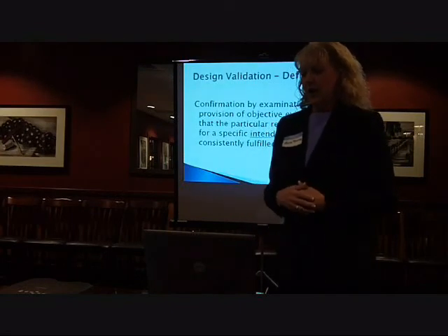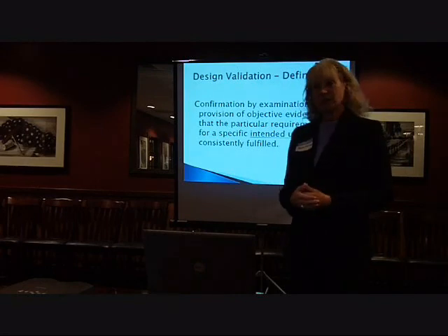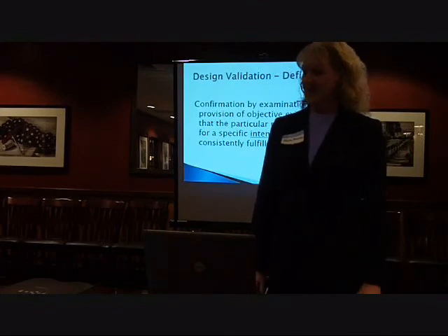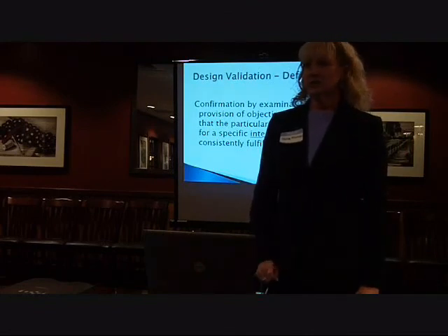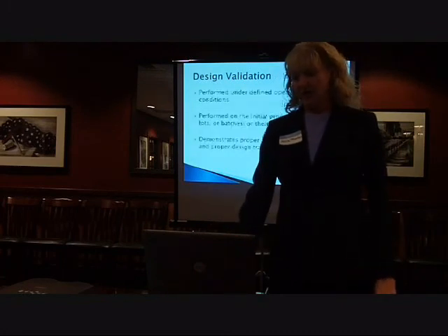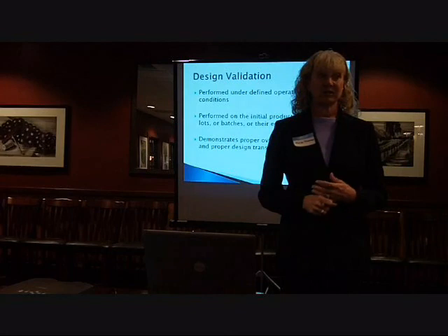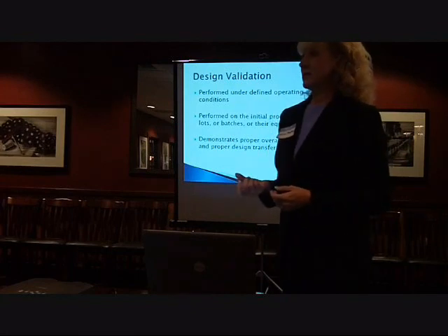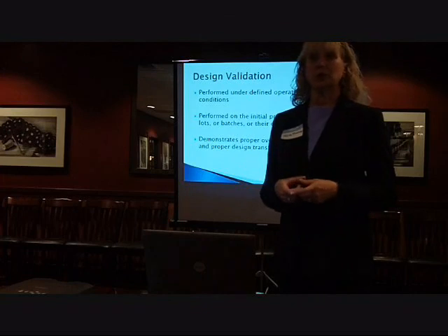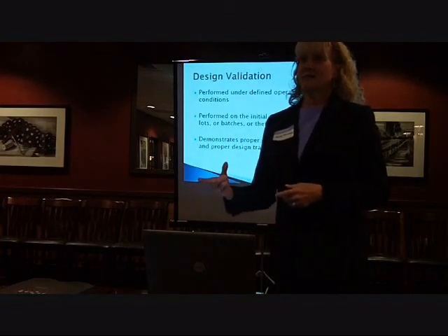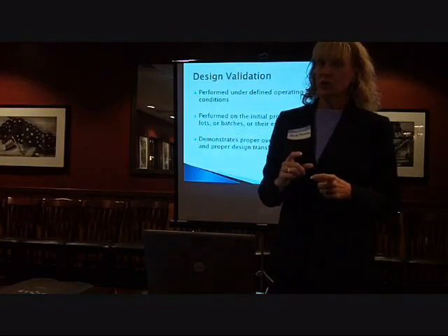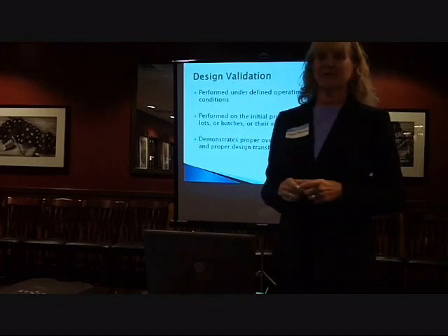Then we're going to go into the validation, which everyone is familiar with, no matter what you're working on. Again, it is objective evidence that it will meet that intended use. So whatever this is really supposed to do, is it able to do it? The thing that's a little different here is that you perform these under the defined operating conditions. So if this is a portable, handheld blood glucose meter, you're going to validate that with the people who are going to use it. And you're going to take units that are coming off of your production line.